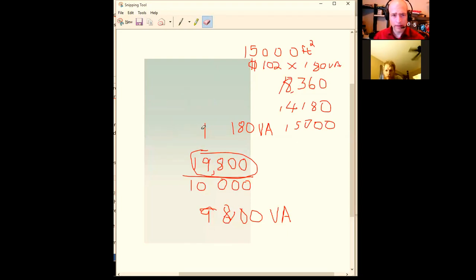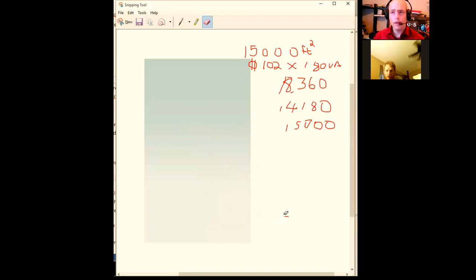And then finally, the third option is if you're looking at K2, you know what the square footage is. The problem with the last one versus this one is we didn't know what the square footage was, so we couldn't really derate at all. This one we would want to derate under K1, because that's what we do under note I, which would give us this answer right here, the 14,180. But the fact that we have this square footage means that's going to be the larger of the two calculations under note K2.